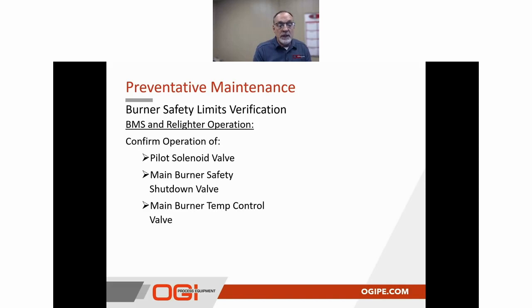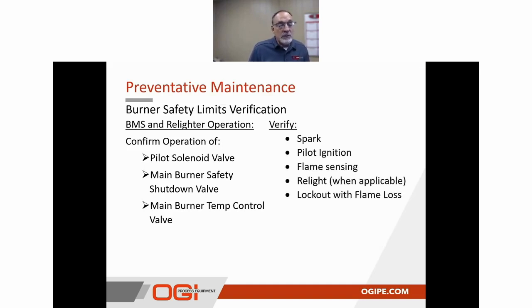In this case, we want to confirm that the pilot and main burner solenoid valves are working properly, and that the main burner temperature control valve is operating the way it should based on different conditions. So in the event that there's a request or a call for heat, we want to make sure that we have spark, that the pilot ignition is working properly, and that we're actually sensing flame. And then in the event of a loss of flame, on a BMS or a relighter system, that the flame is relit when applicable. In some cases, a client has requested that it not be, like for a power burner. In the event that there is a flame loss, or in this case a relighter attempt, and it's not relit, there's a lockout based on flame loss.